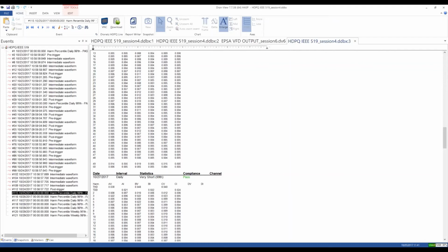It records the 10-minute intervals because that's just a regular journal interval by the HDPQ family. But unless you set the journal interval for 3 seconds, which I do not recommend, certainly it's not needed for this application. So unless you do that, you are not going to get that 3-second data in the database, because there's no need for it. The instrument maintains all the statistical analysis, and products that do things like that, the reason why they do it is because they can't maintain that statistical data. That has to be done offline in a spreadsheet or using some other math engines to do that for you. But the HDPQ family does this automatically for you in the background while you're monitoring. You don't have to do a thing.